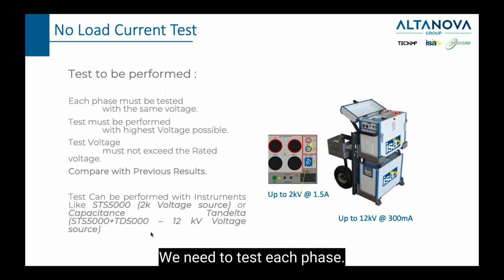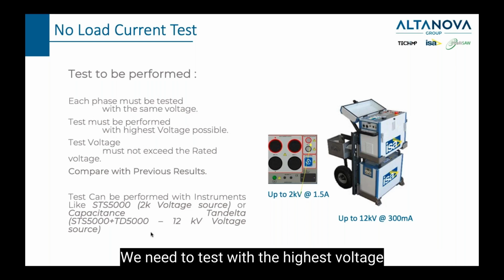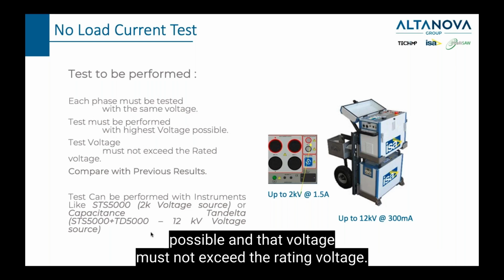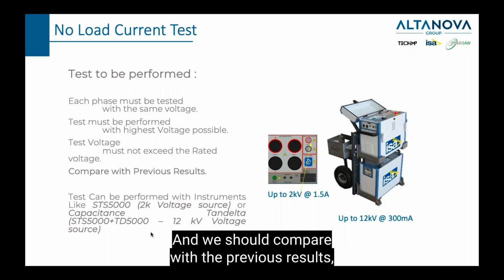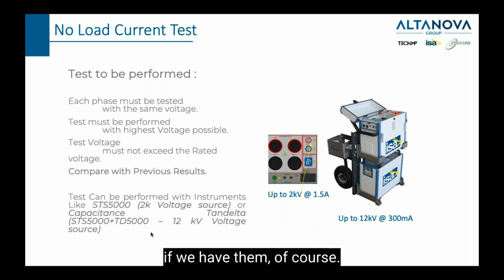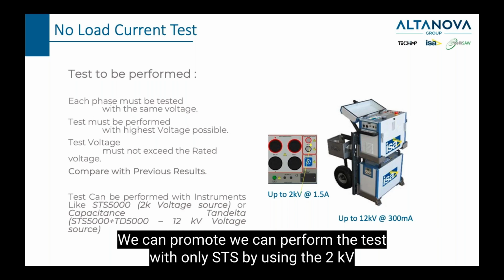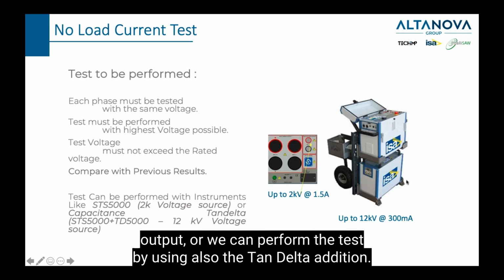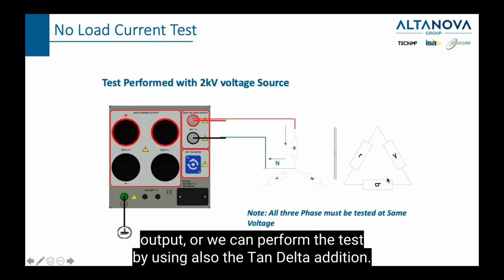We need to test each phase. We need to test with the highest voltage possible, and that voltage must not exceed the rated voltage. And we should compare with the previous results if we have them, of course. We can perform the test with only STS by using the 2 kV output, or we can perform the test by using also the tan delta addition.